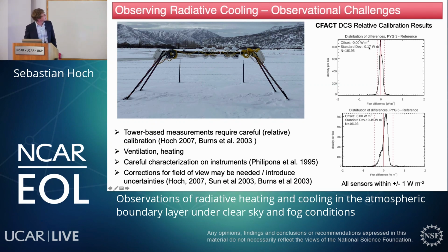And when you do this, here's for this relative calibration at the Deer Creek supersite, you're seeing these three pyrgeometers against the reference, which, here I'm using the reference as the mean of all the 4 instruments. You're seeing that you get a very small standard deviation. Here's one that wasn't performing quite as well, but you're seeing that these differences are well within plus minus 1 watt per square meter.